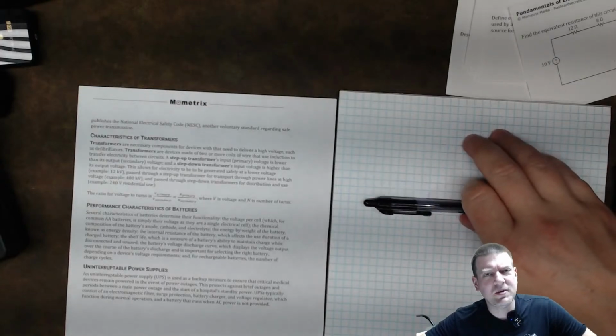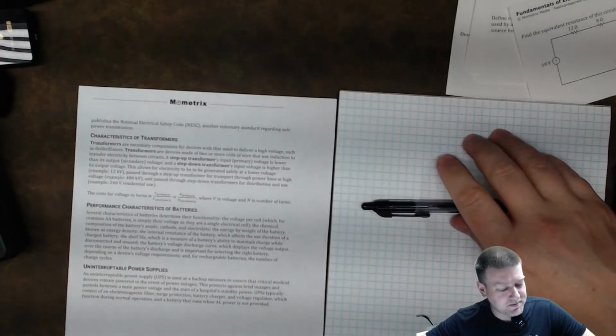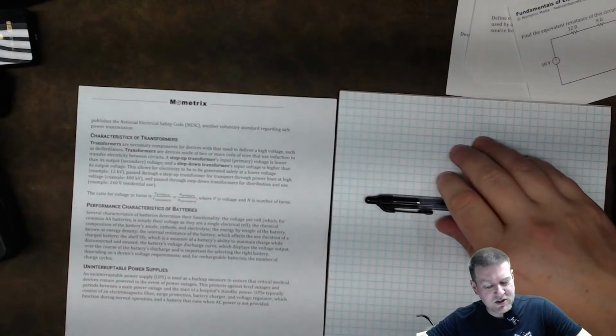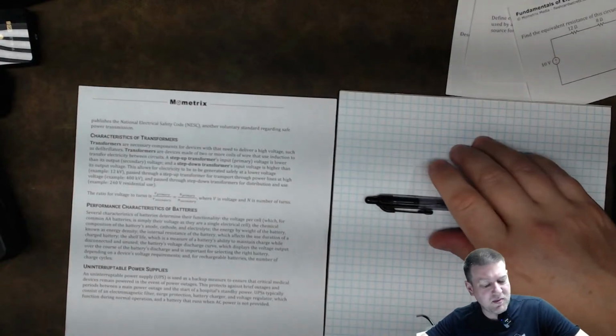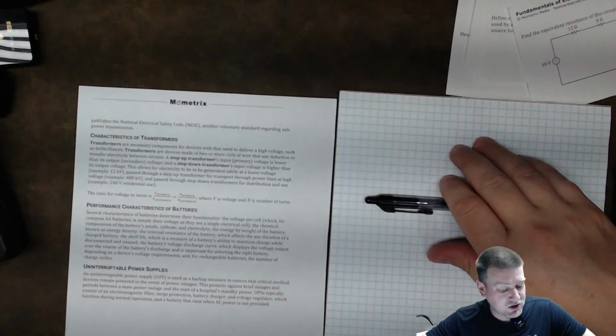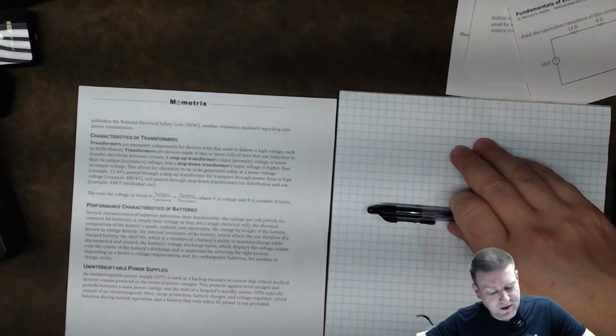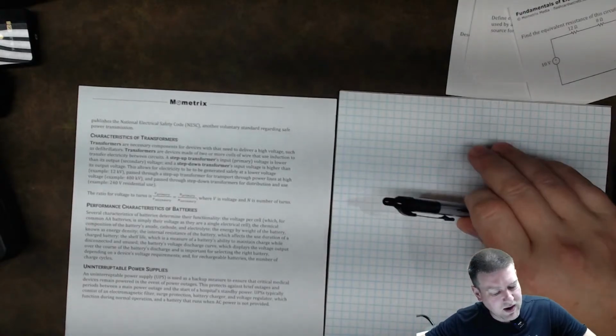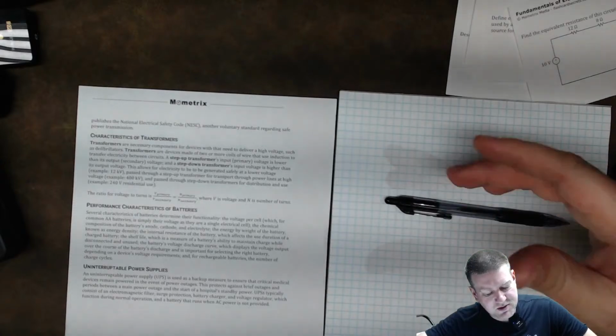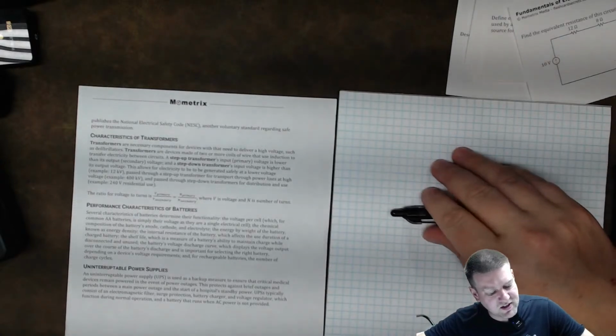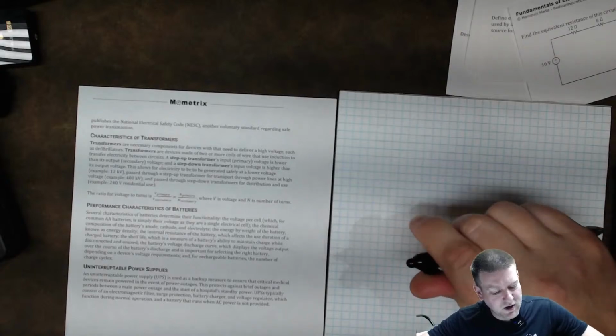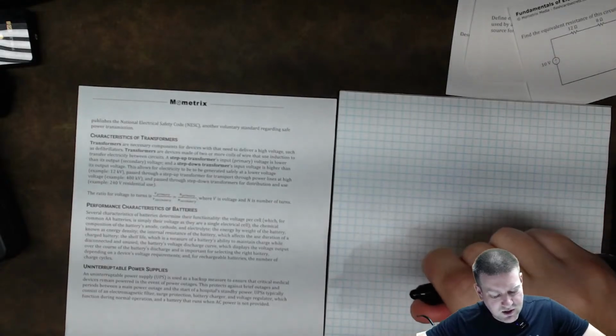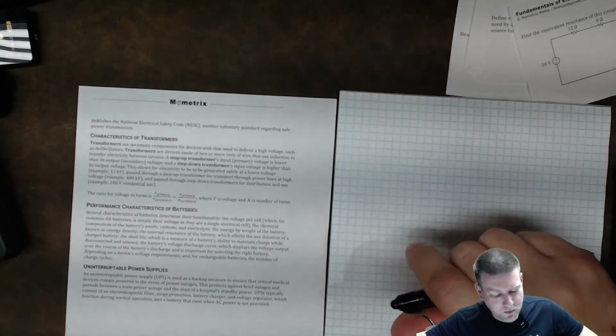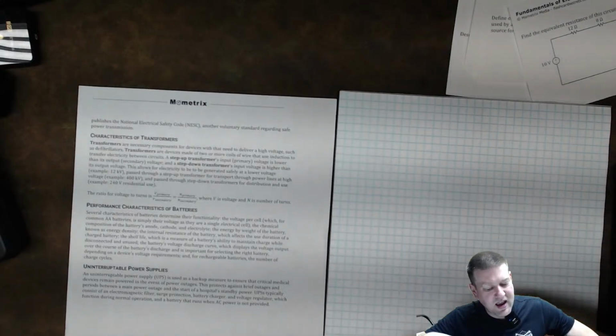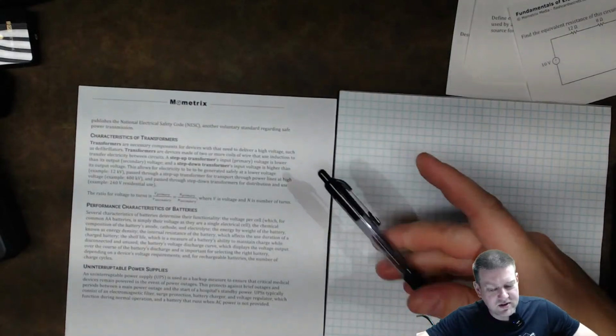Uninterruptible power supplies, UPS systems, are used as a backup measure to ensure critical medical devices remain powered in the event of a power outage. This protects against brief outages and periods of main power outage until the start of hospital standby power. UPSs generally consist of an electromagnetic filter, surge suppression, battery charger, and voltage regulator which function during normal operation, plus a battery that runs when AC power is not provided.